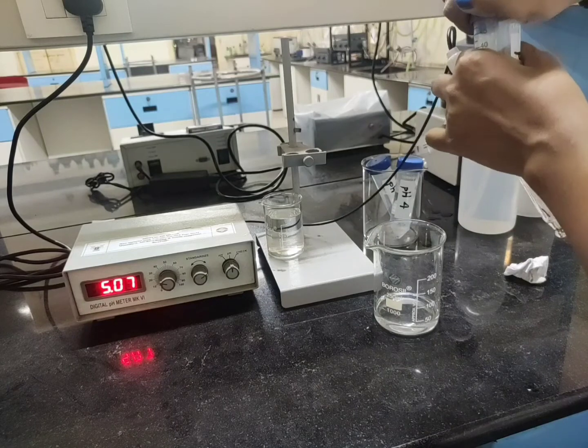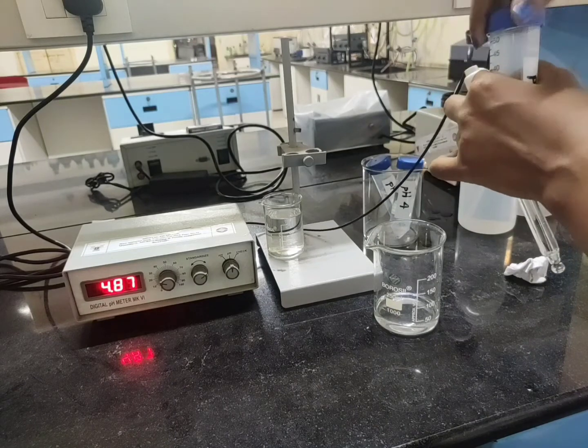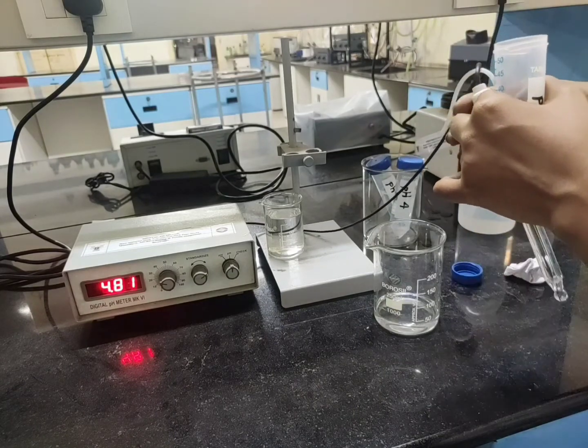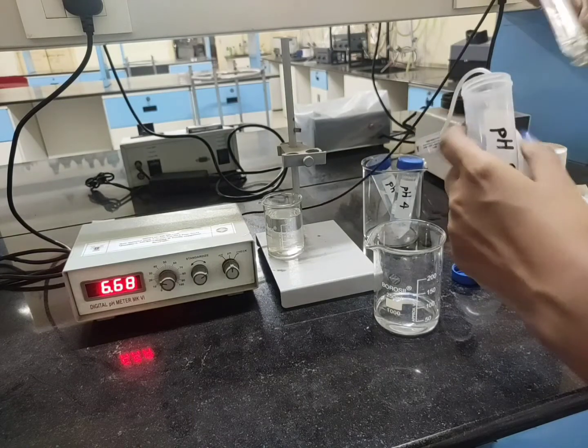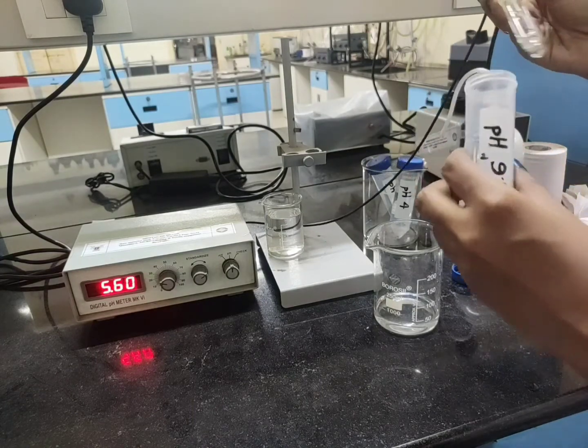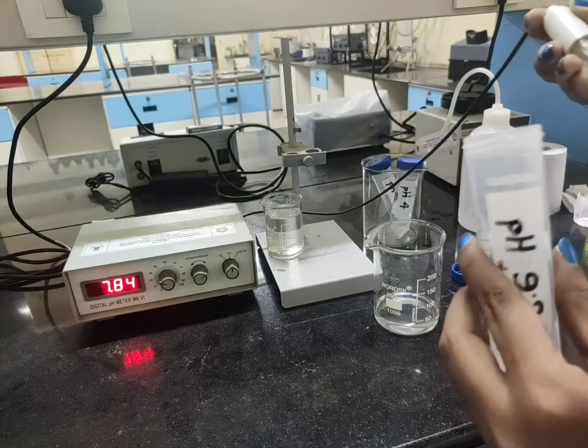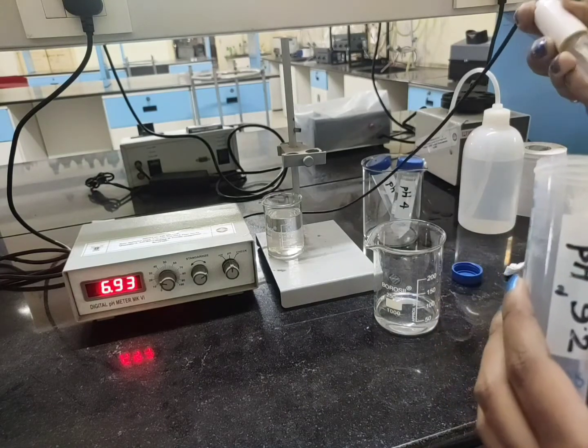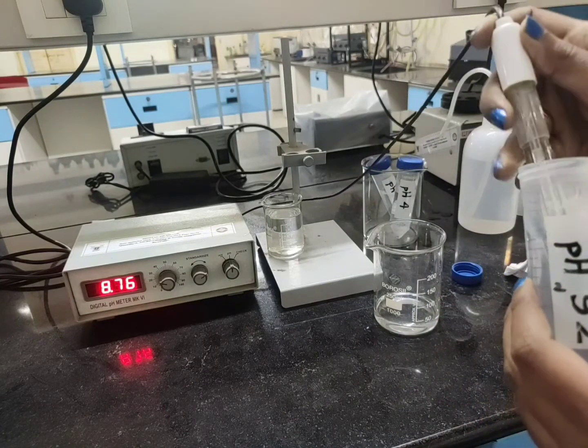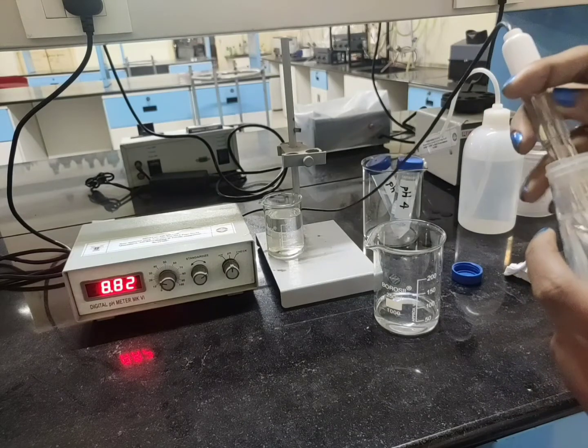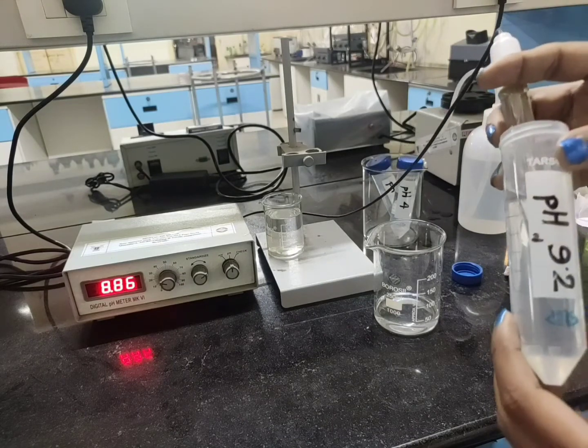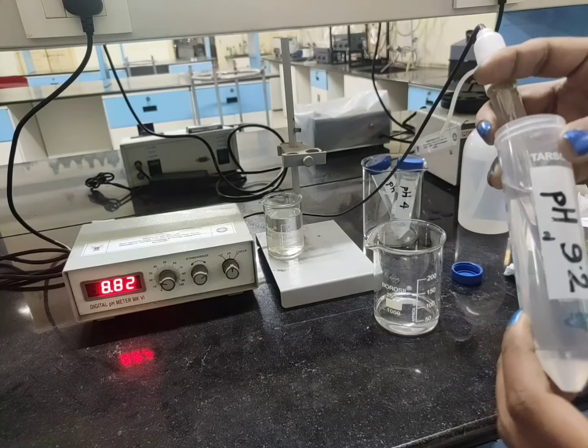So for calibration we always calibrate at 3 points. One we give for neutral, then we have acidic, and the last one is alkali. Now in the alkali, the buffer we are having is 9.2. You also get a pH of around 10. So whichever it is, you have to make sure that it is the alkali buffer, and then you have to calibrate the instrument accordingly.